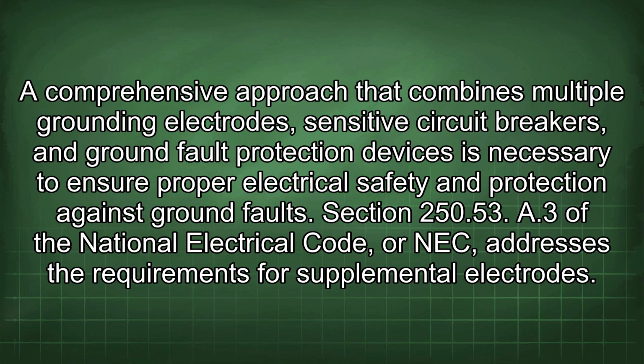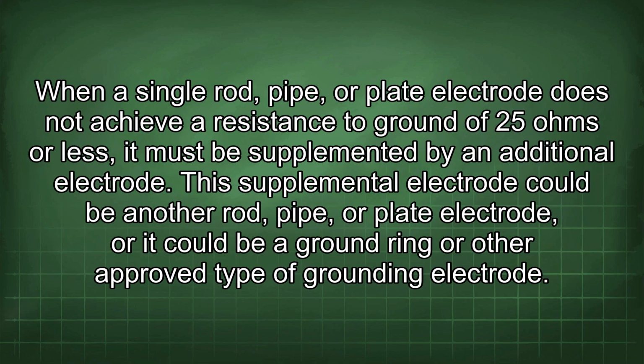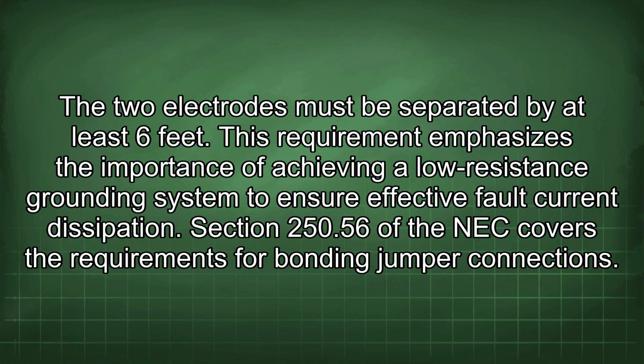Section 250.53(A)(3) of the National Electrical Code, or NEC, addresses the requirements for supplemental electrodes. When a single rod, pipe, or plate electrode does not achieve a resistance to ground of 25 ohms or less, it must be supplemented by an additional electrode. This supplemental electrode could be another rod, pipe, or plate electrode, or it could be a ground ring or other approved type of grounding electrode. The two electrodes must be separated by at least 6 feet. This requirement emphasizes the importance of achieving a low-resistance grounding system to ensure effective fault current dissipation.